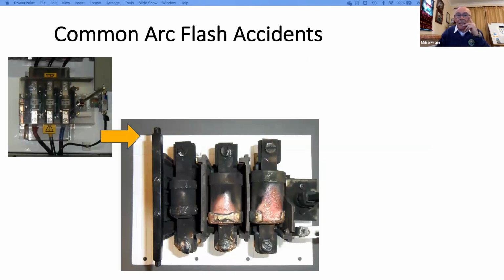It's another one where I was asked to undertake an investigation into an arc flash incident, which caused injury to a facilities technician who had been fault finding on a chiller pump star-delta motor set, at a big IT manufacturer. The picture on the left is a healthy unit, and on the right is a damaged switch fuse. And my conclusions were that the arc flash started on the load side of the switch fuse, which is there, but it migrated to the line side.